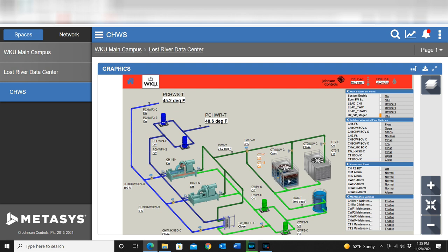In order to keep it from getting too cold. Now, one thing you do not want to do on a chiller, as many of you all are aware, is getting that condenser water too cold. Some machines will actually trip and have other issues if you get that water too cold. But this is basically an overview of a plate frame chilled water system.